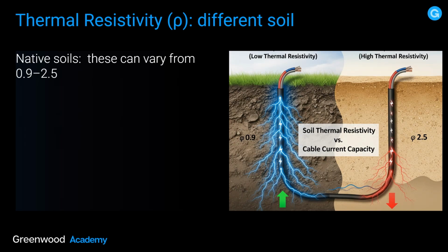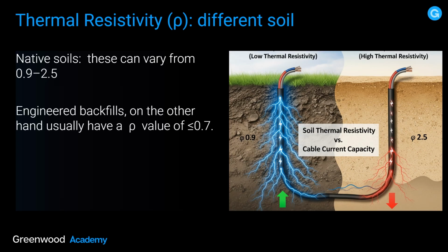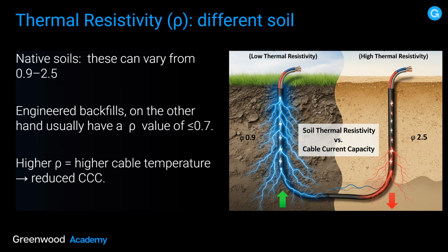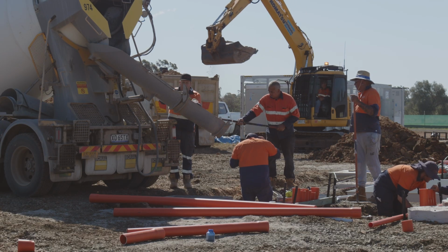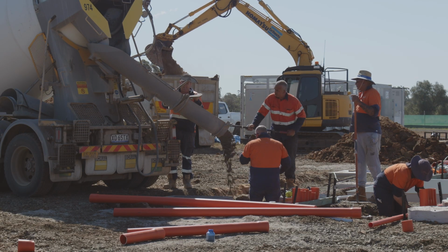Now, native soils can vary from 0.9 to 2.5 when it comes to thermal resistivity. Engineered backfills, on the other hand, usually have a value of less than or equal to 0.7. The higher the rating, the higher the cable temperature, the reduced CCC. Now, I mentioned engineered backfills. What we're talking about is a trenching situation where the native soil has been taken away and disposed of, and then as an option, an engineered backfill has been put in because it has a lower thermal resistivity.